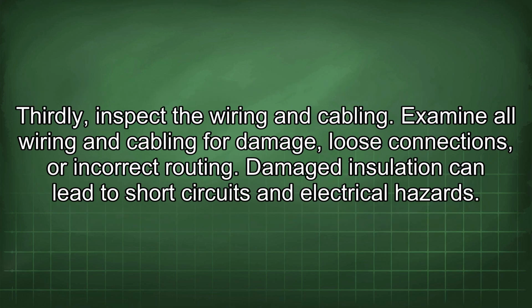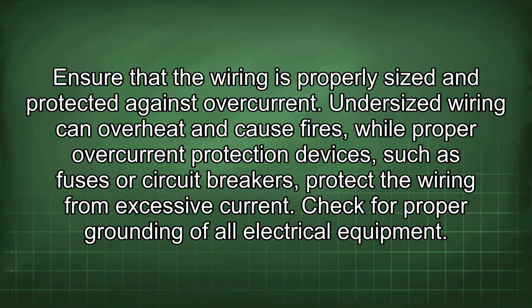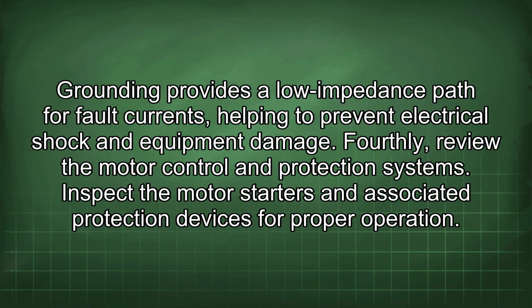Thirdly, inspect the wiring and cabling. Examine all wiring and cabling for damage, loose connections, or incorrect routing. Damaged insulation can lead to short circuits and electrical hazards. Ensure that the wiring is properly sized and protected against overcurrent. Undersized wiring can overheat and cause fires, while proper overcurrent protection devices, such as fuses or circuit breakers, protect the wiring from excessive current. Check for proper grounding of all electrical equipment. Grounding provides a low impedance path for fault currents, helping to prevent electrical shock and equipment damage.